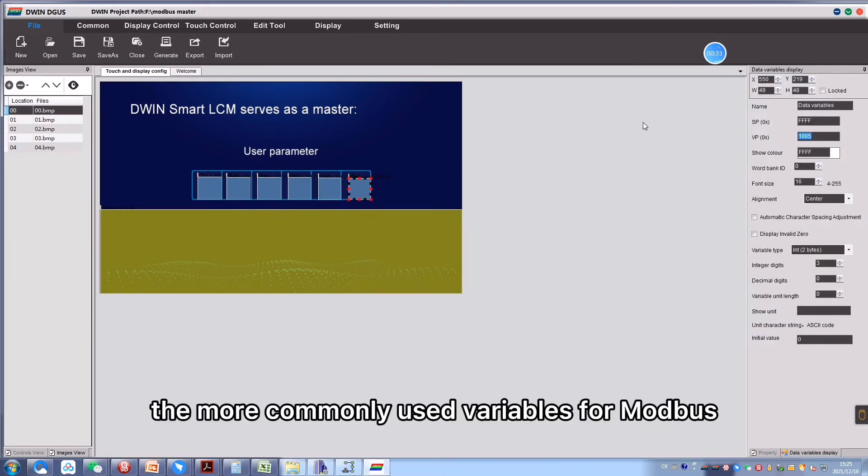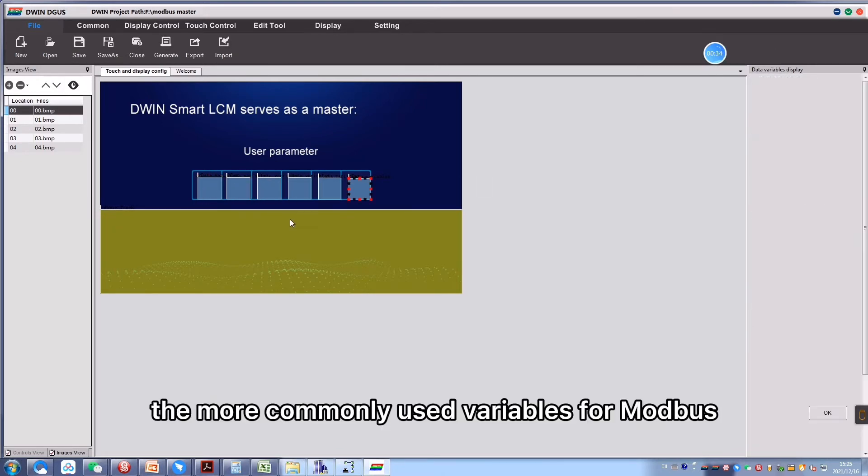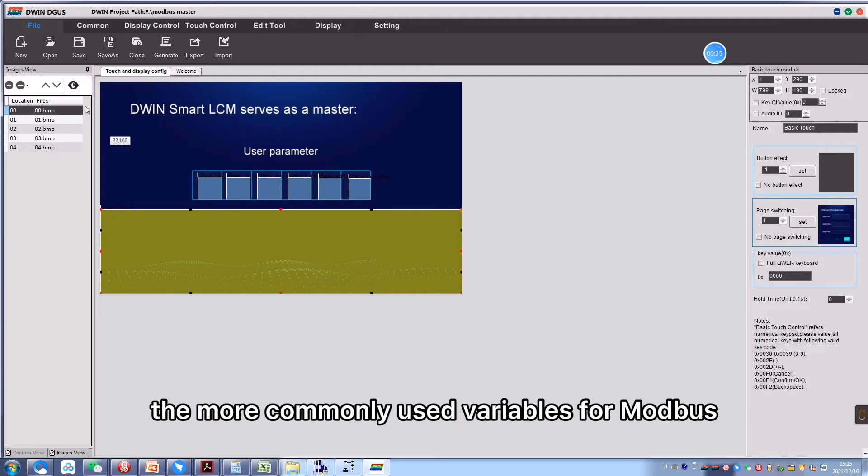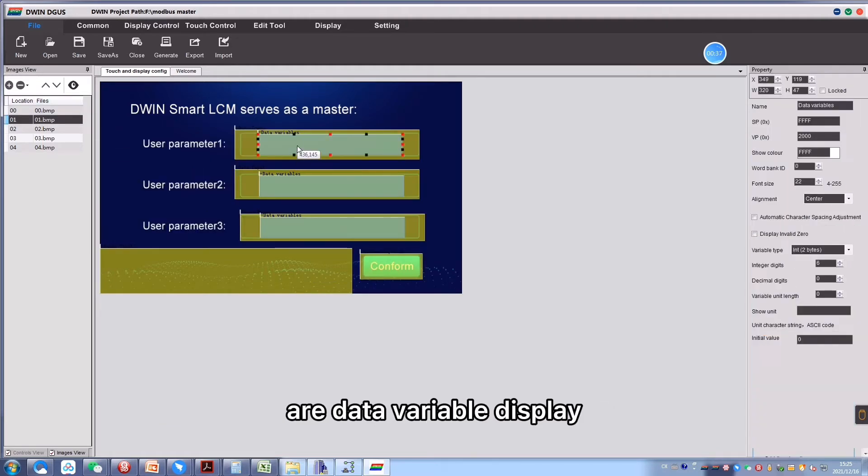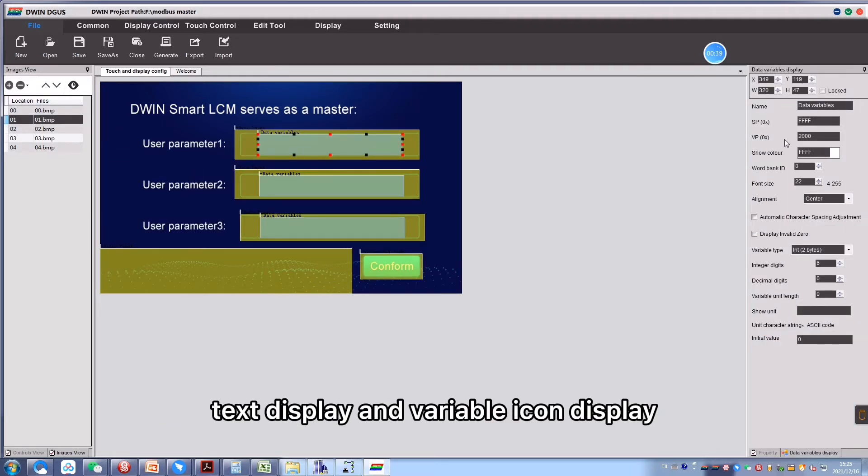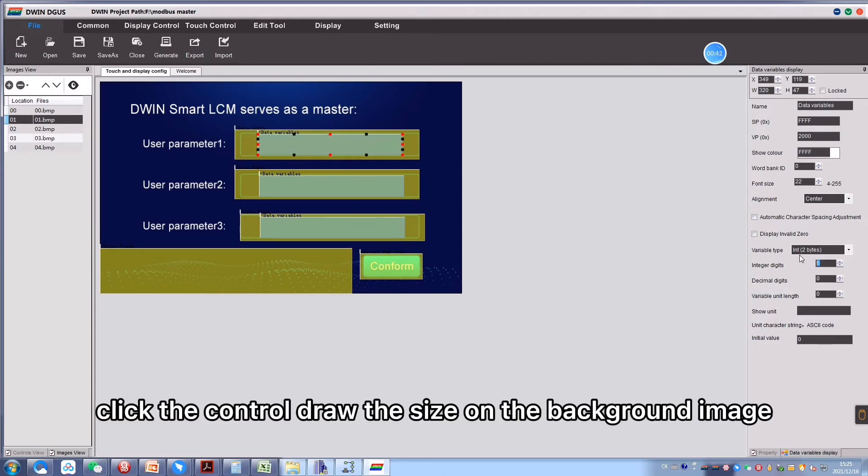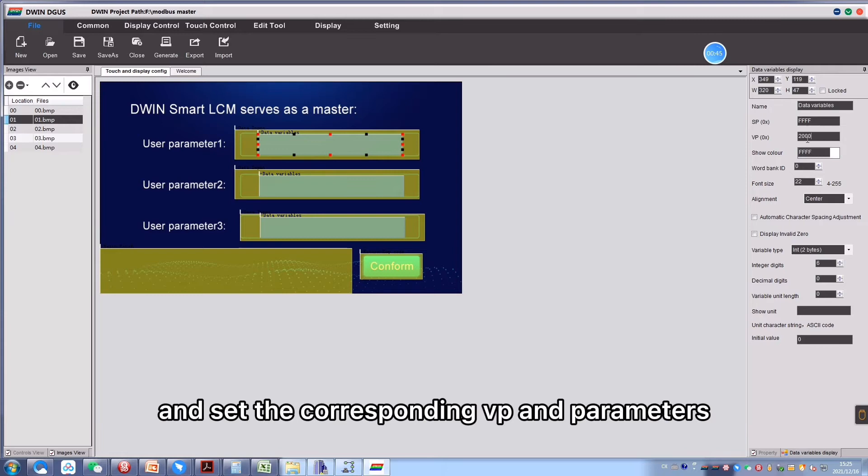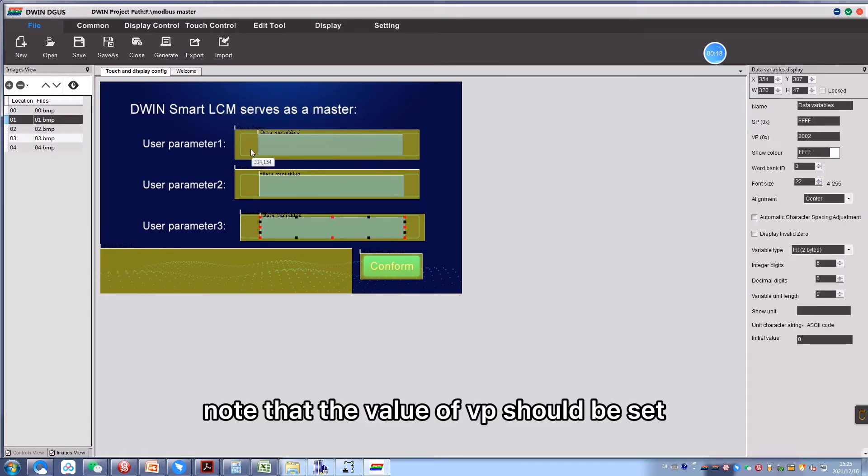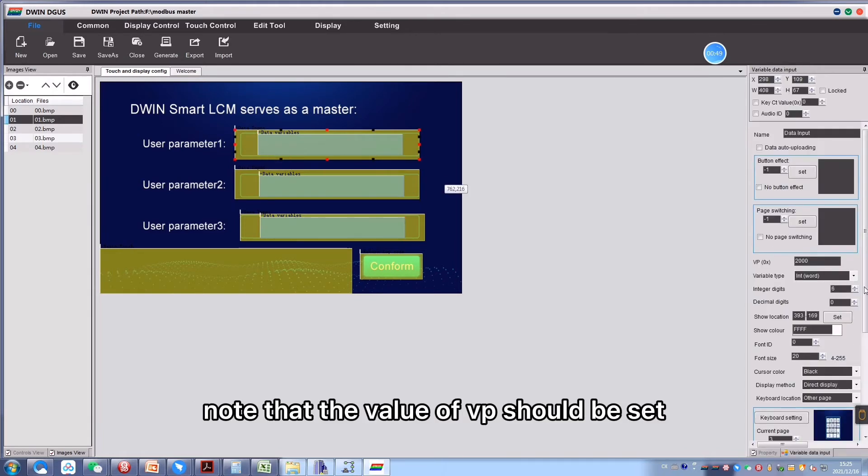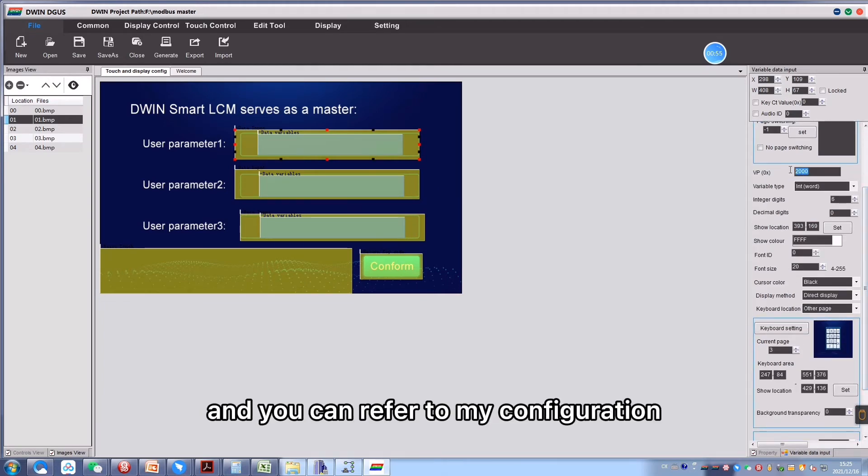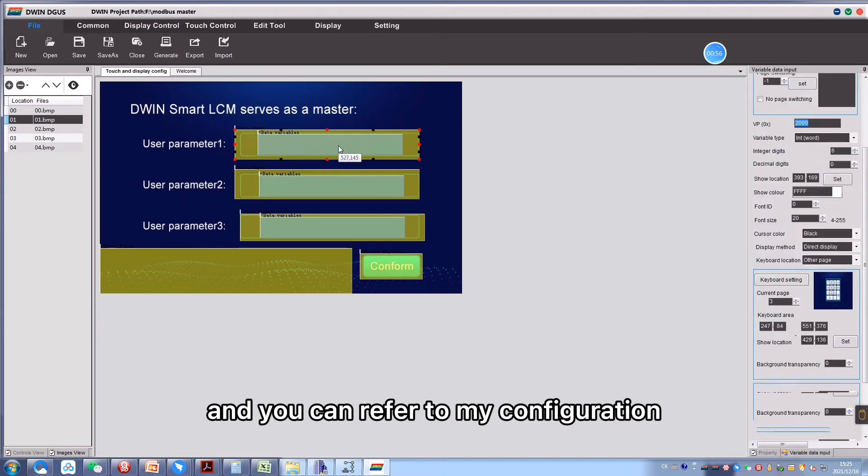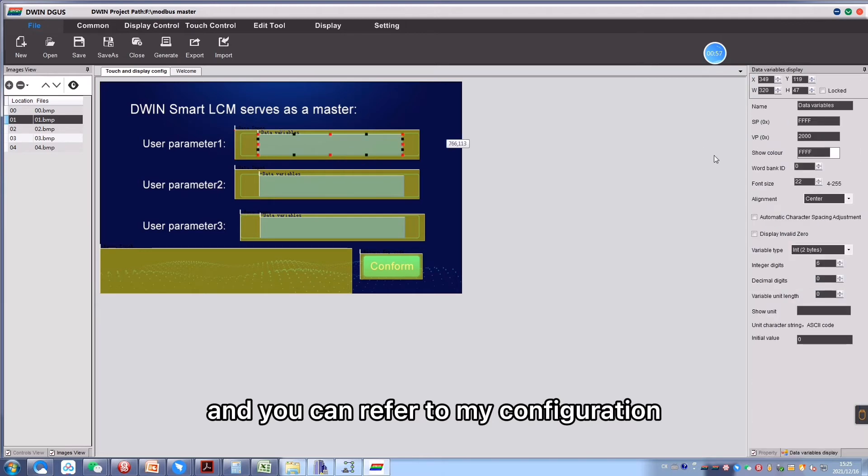The more commonly used variables for Modbus are data variable display, text display, and variable icon display. Click the control, draw the size on the background image, and set the corresponding VP and parameters. Note that the value of VP should be set to 1000 and above. I have made the project here, and you can refer to my configuration.